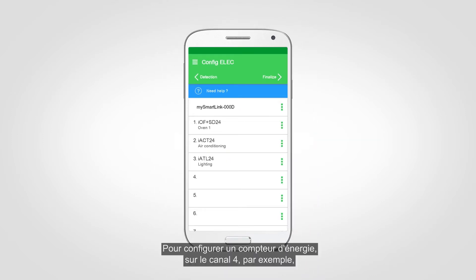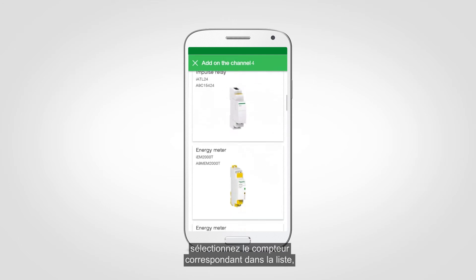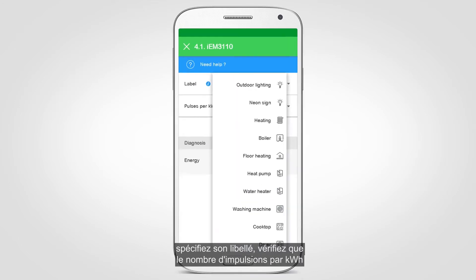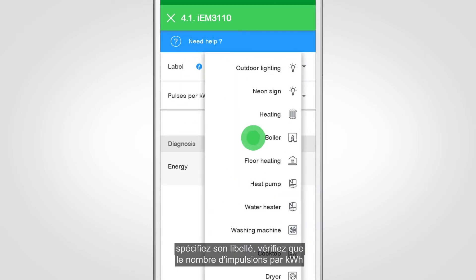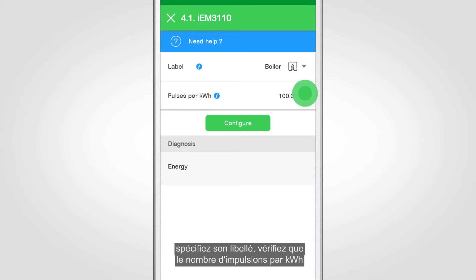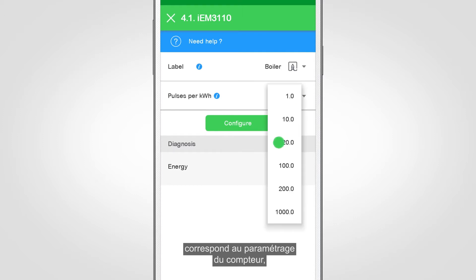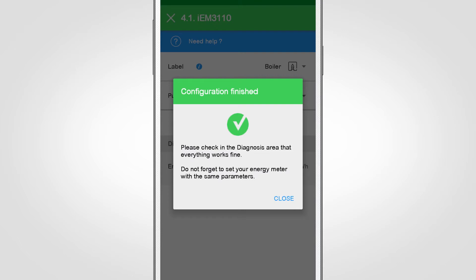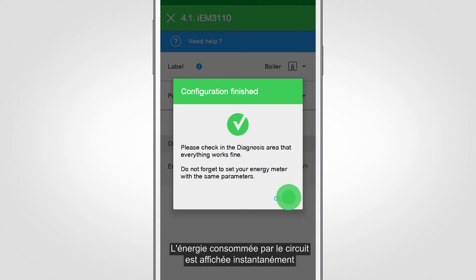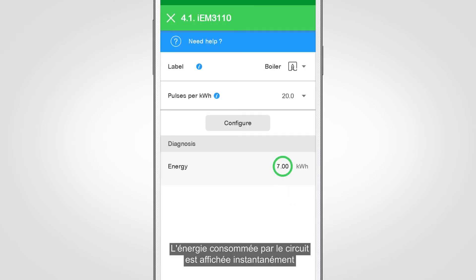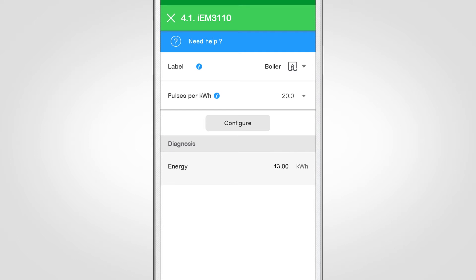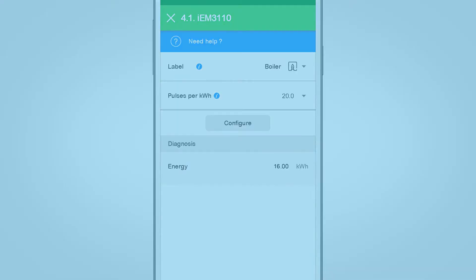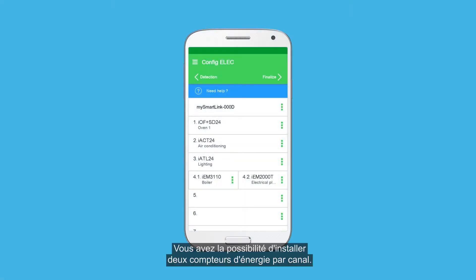To configure an energy meter on channel 4, for example, select the corresponding meter from the list, specify its label, verify that the number of pulses per kilowatt-hour corresponds to the parameters of the meter, and validate the configuration. The energy consumed by the circuit is instantly displayed in the diagnosis section. You can install two energy meters per channel.